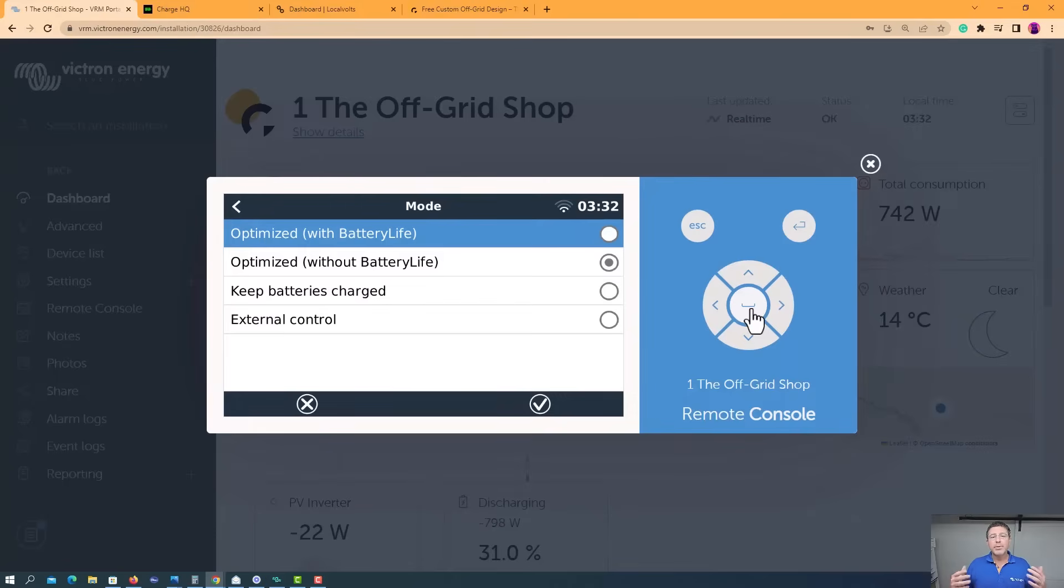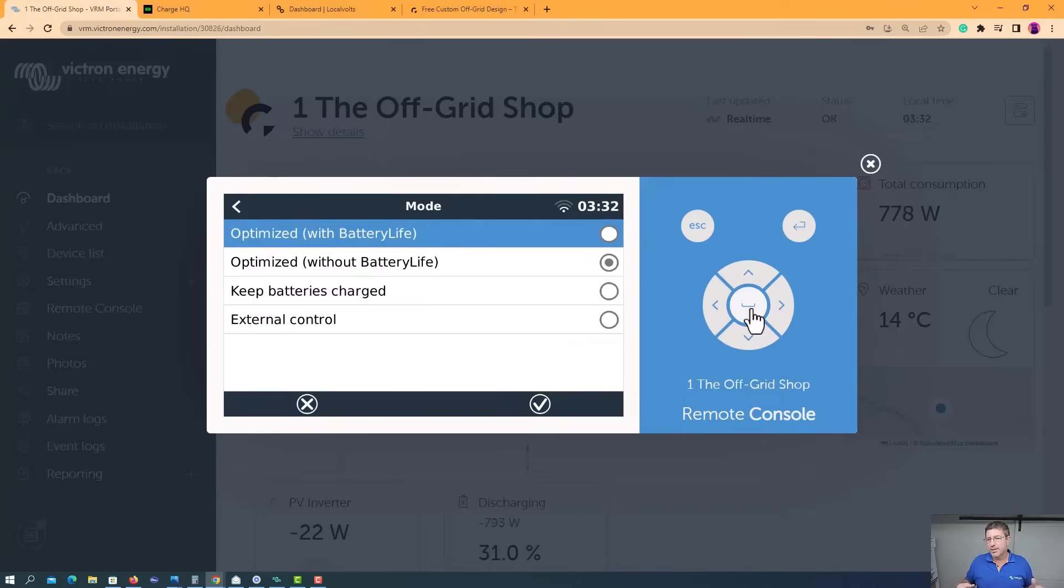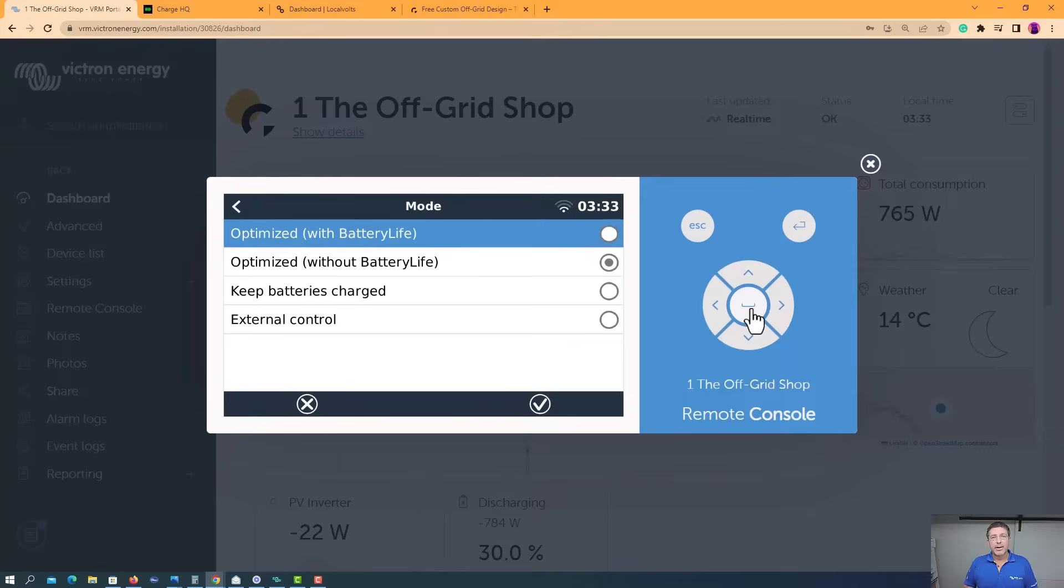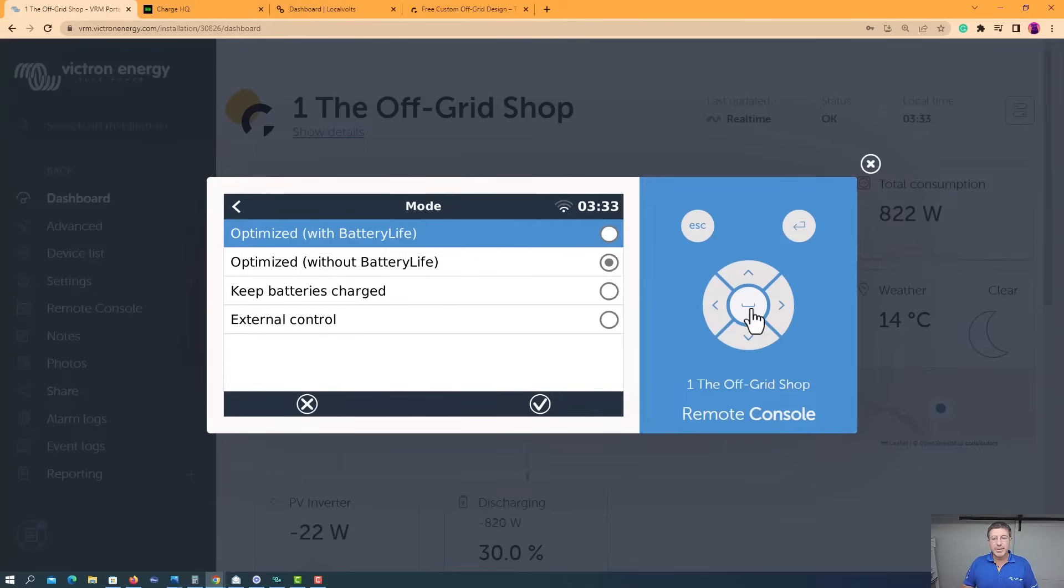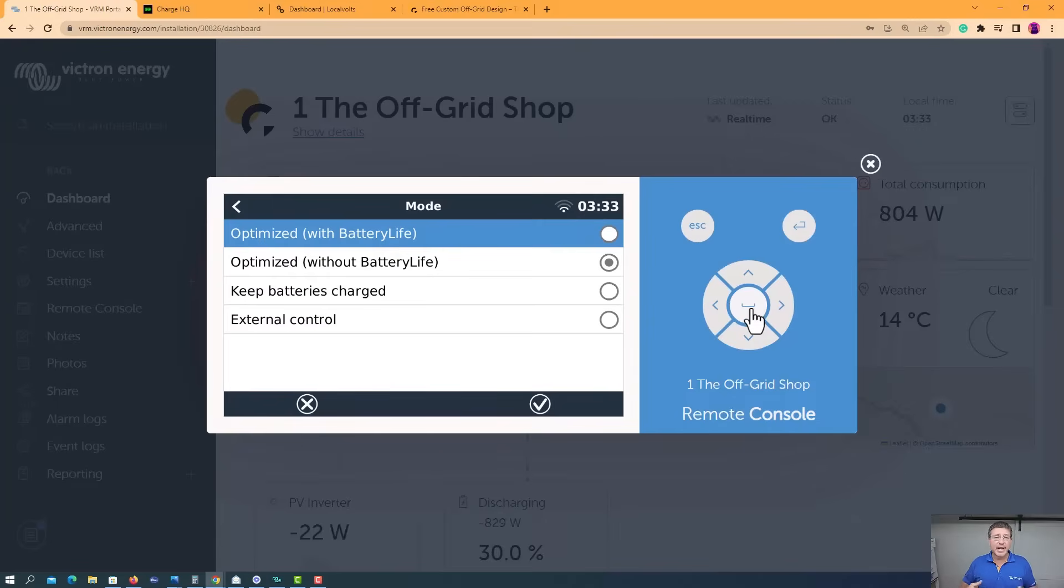So if it is 100% reliable power that you want, it's really important that you probably use a grid and a generator as a backup in these systems. That backup source, like a generator, is really important if you want 100% reliable power. Now, the difference between optimize with battery life and optimize without battery life. I run mine optimized without battery life. What it actually does, it's designed to basically take the batteries to 0% every single day. Literally just use as much as you can. What optimize without battery life will do, it'll actually let your system run down to zero if necessary. If you use all your energy overnight, most hybrid systems when the grid's available, that's what they're designed to do because it's mainly more about a financial return, where an off-grid system is about I want power, I've got no power.